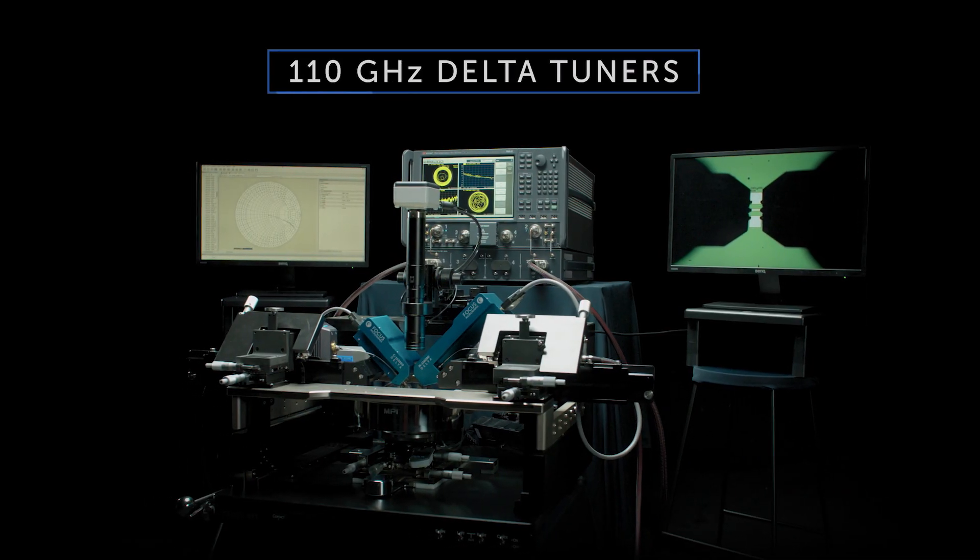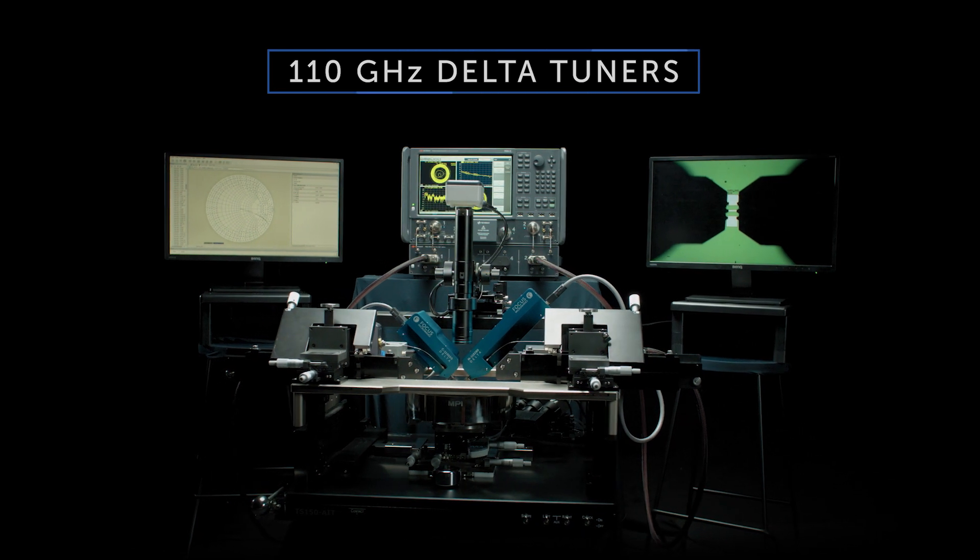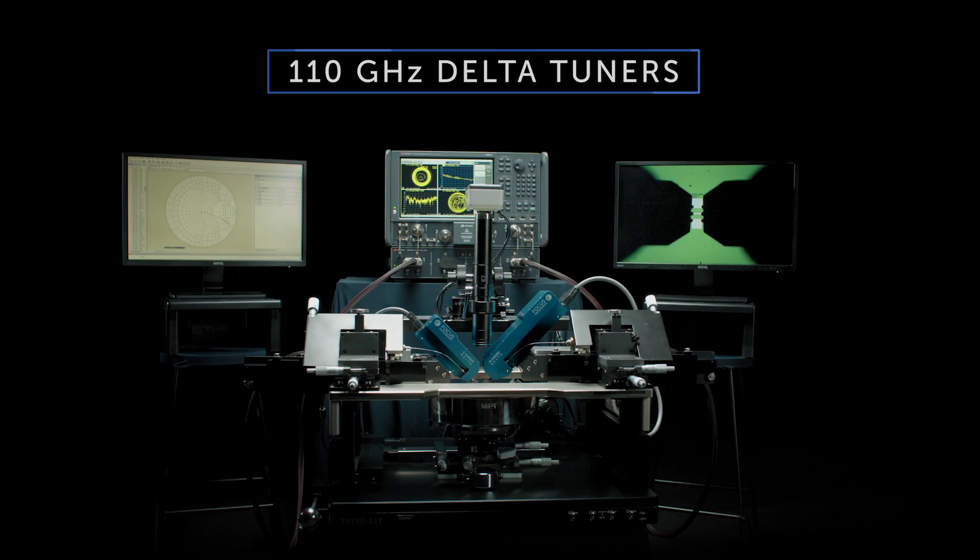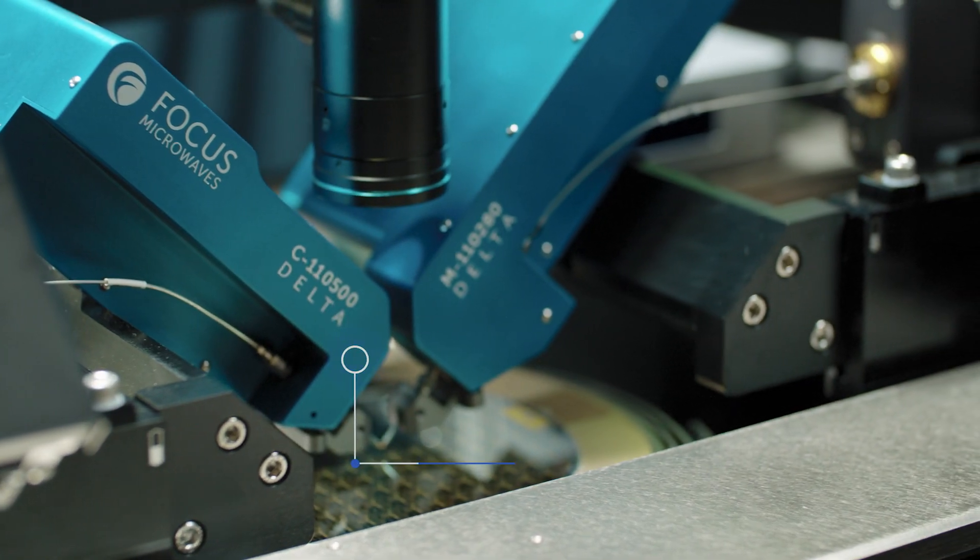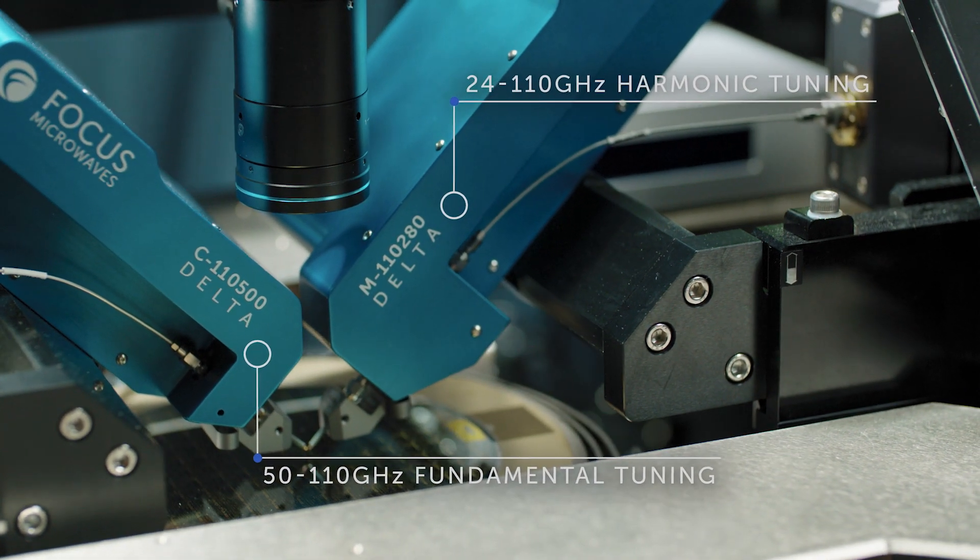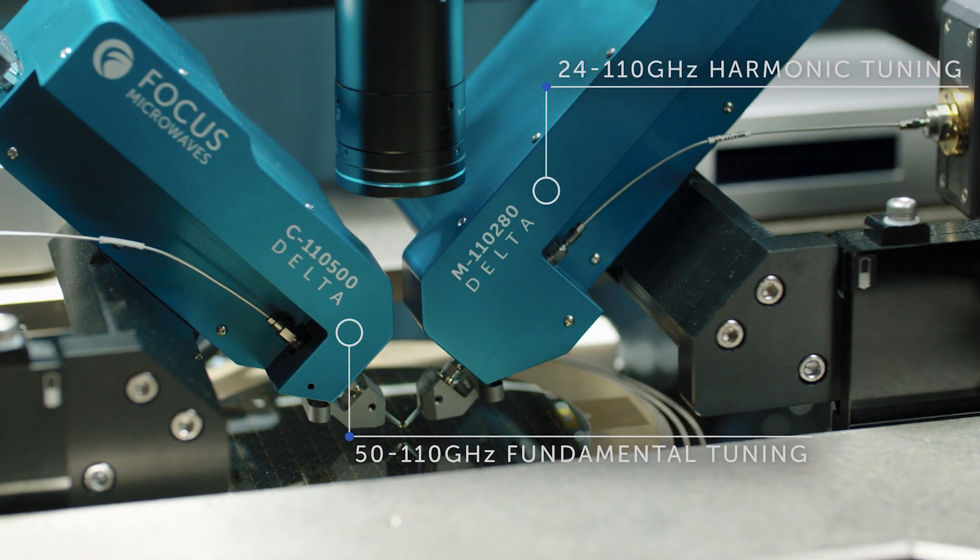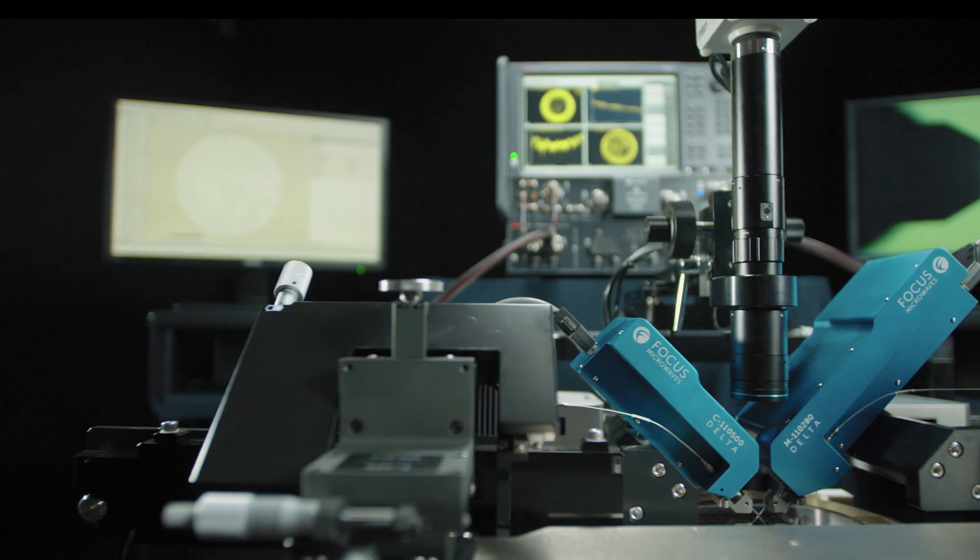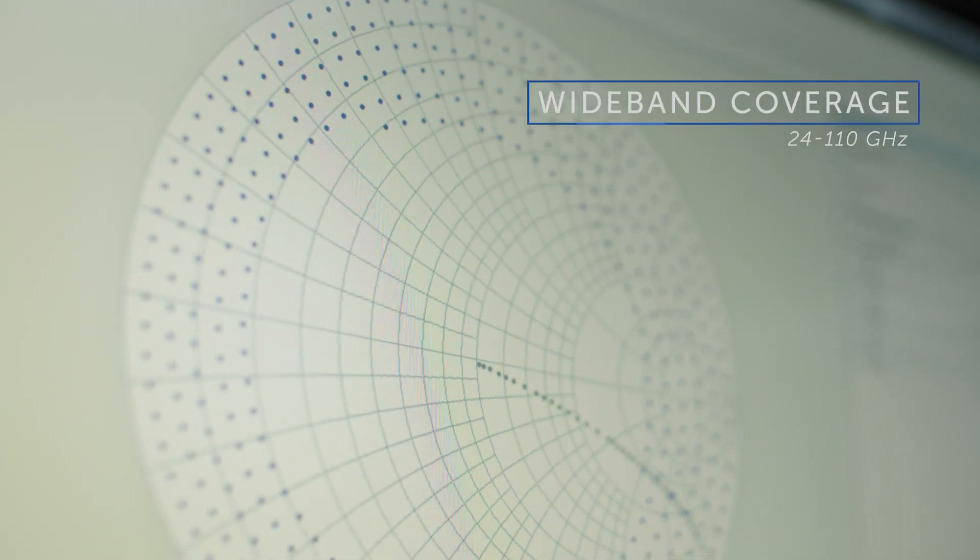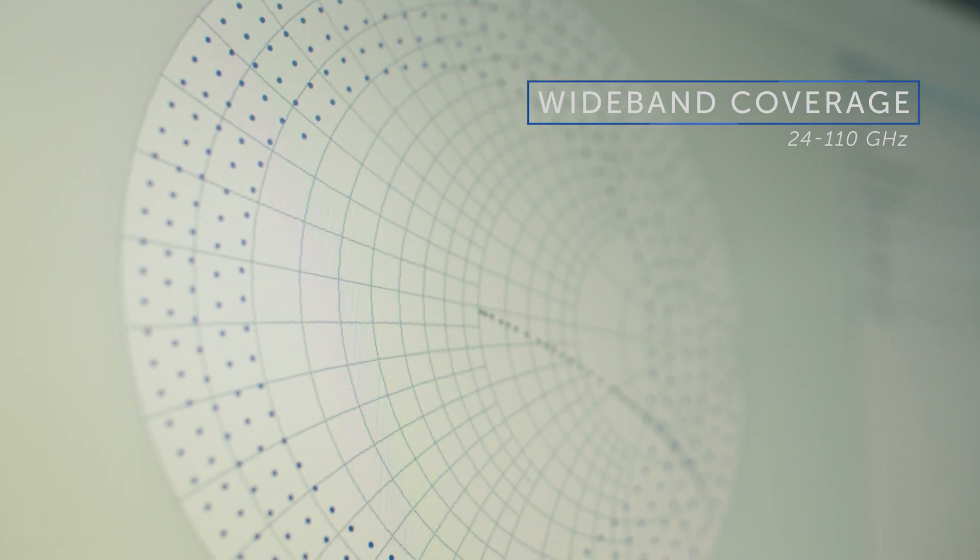The all-new 110 GHz Delta tuners allow for wideband tuning with maximum gamma of 24 to 110 GHz. They are designed for broadband, non-50 ohm measurements on millimeter wave devices using three independently controlled precision tuning probes. Users can select ultra-wideband probes for best frequency coverage or narrowband high VSWR probes for specific applications.